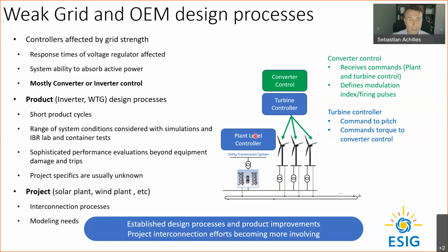Most of the weak grid aspects relate to a fast interaction with the grid and affect mostly the converter control. The aspects that have to be tweaked are usually related to sensing the condition in the grid and adapting the response of the IBR to that. So having prescriptive responses, like injecting reactive power no matter what, or absorbing reactive power no matter what—those are the type of things that are not good for weak grids.